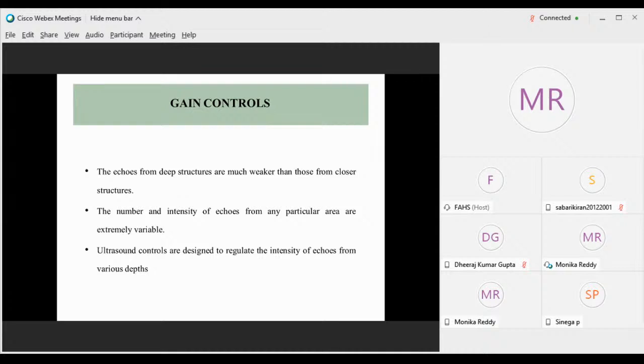Echoes from deeper structures will be weaker and will get attenuated there itself. They don't reach the transducer, so we have to boost them. By using these controls, we can boost and adjust these weaker signals in order to provide a proper image. The number and intensity of echoes from any particular area are extremely variable, so ultrasound controls are designed to regulate the intensity of echoes from various depths.